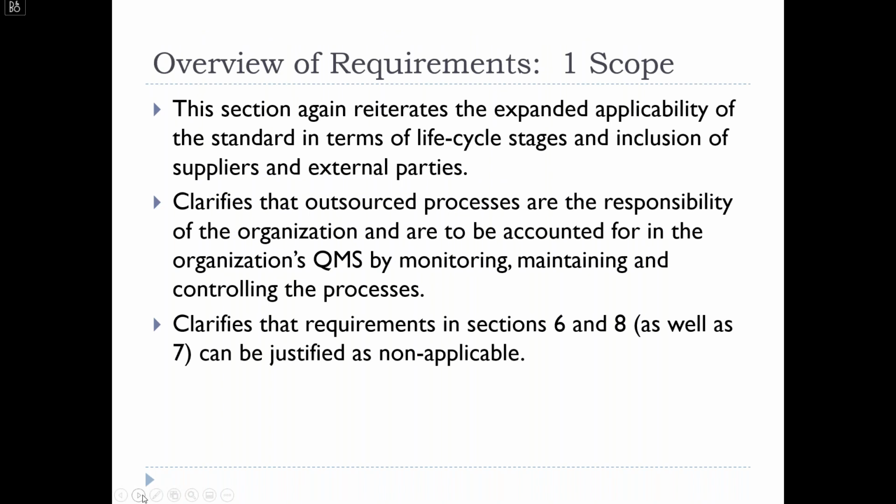Section 1 scope, again, reiterates the expanded applicability of the standard in terms of life cycle stages and different suppliers and external parties, not just the medical device manufacturers themselves. This next bullet point, I think, is one of the most important points in this entire presentation. Outsourced processes are the responsibility of the organization and are to be accounted for in the organization's QMS by monitoring, maintaining, and controlling the processes.